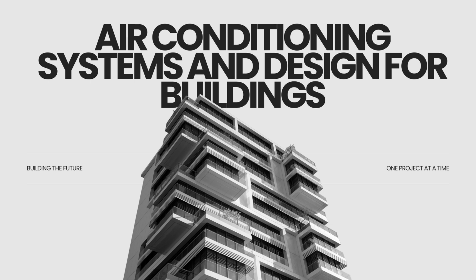There are definitely trade-offs. The main one is usually the higher initial cost. A split-type system is typically more expensive up front to purchase and install compared to a window-type air conditioner of similar capacity. This initial investment can be a barrier for some. Additionally, installation and maintenance can be more complex. Because you have two separated components connected by refrigerant lines, installation requires careful running and connecting of those lines, properly insulating them, vacuuming the system to remove air and moisture, and accurately charging it with refrigerant. It's not a simple plug-and-play like a window unit.